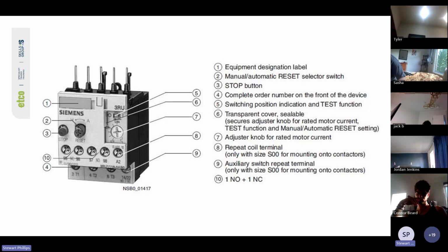Yep. 6, so you've got a transparent cover. It's sealable, so it secures the adjuster knob for rated motor current, test function, and manual automatic reset settings. You've got an adjuster knob for rated motor current, a repeat coil terminal, so don't worry about that, an auxiliary switch repeat terminal, and one normally open and one normally closed auxiliary contact, which you can sometimes use for an indication light, or for the coil of your contactor. So most overload relays plug into the bottom of the contactor. I haven't seen many that don't. We've got a few here in the workshop, but usually they're quite a bit more expensive than the ones that just plug into the bottom of the contactor.